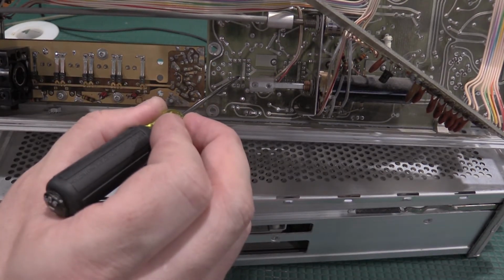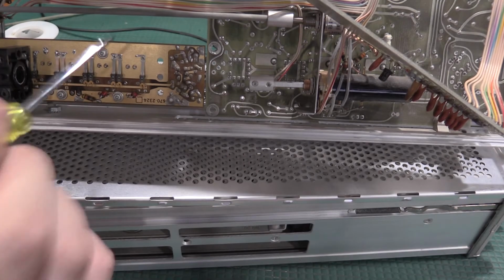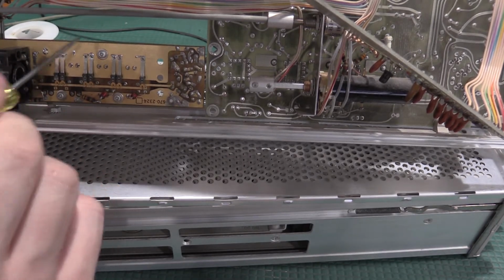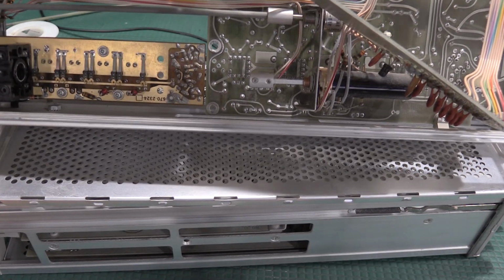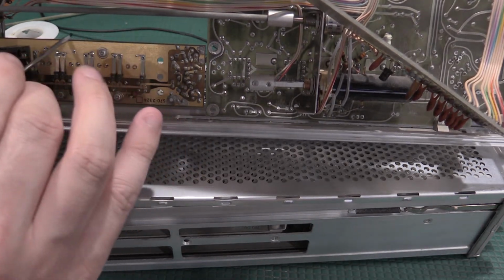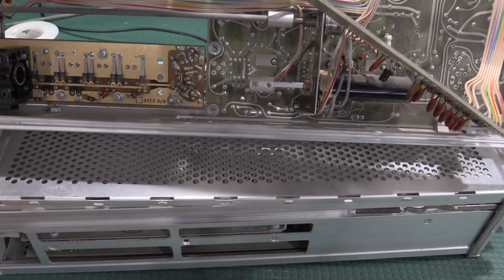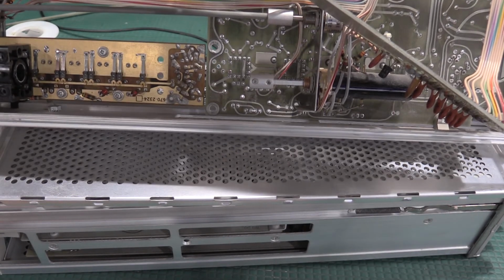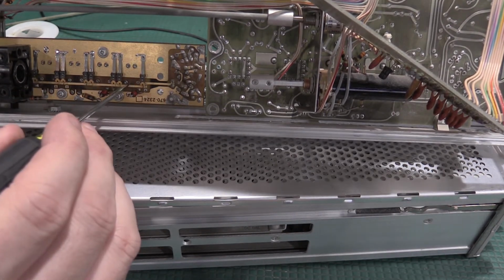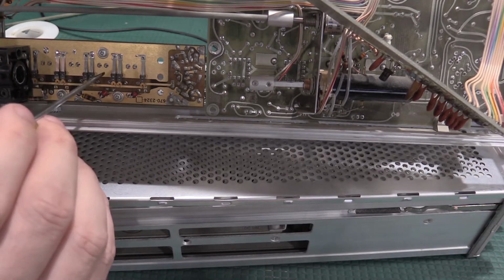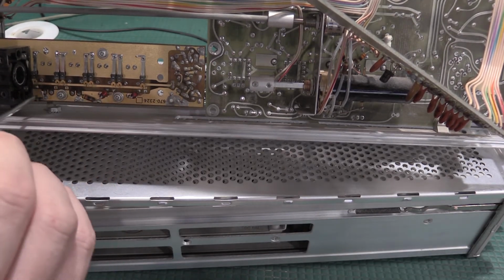And this is where it leaves this board and goes into the rest of the plug-in. Per the manual, this is a very special board material. Do not use anything harsher than isopropyl alcohol on these. You can actually damage the board material. That's per Tektronix's service manuals. So only clean these with isopropyl alcohol, nothing more aggressive.